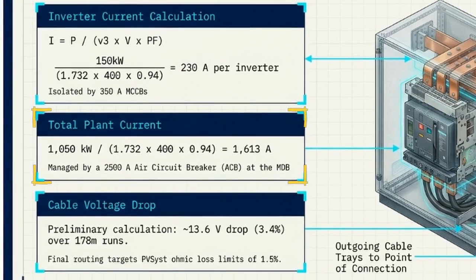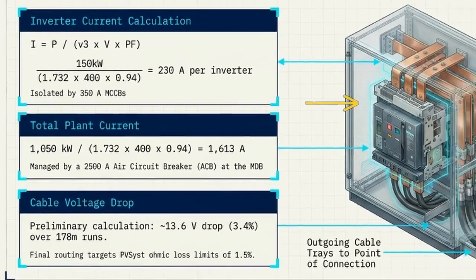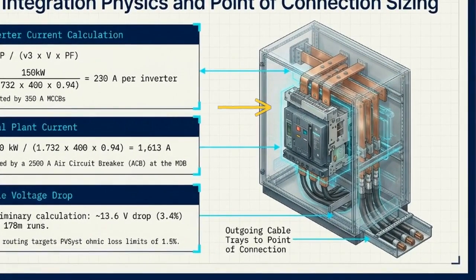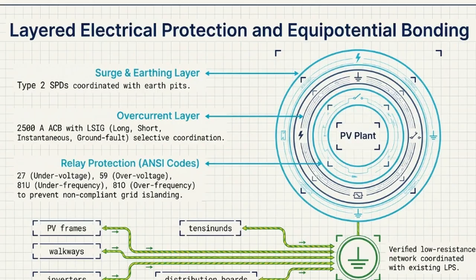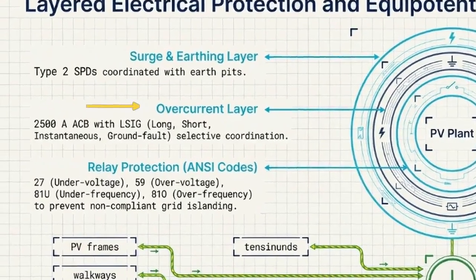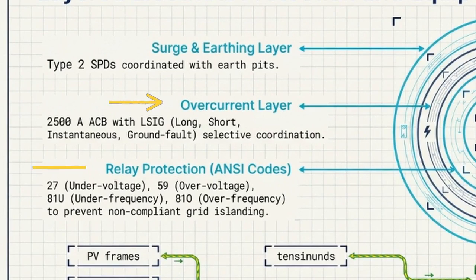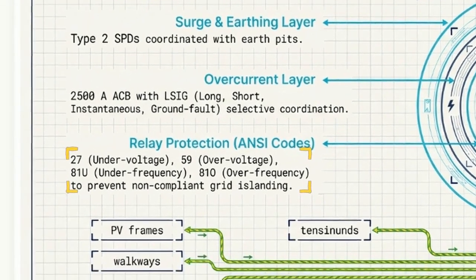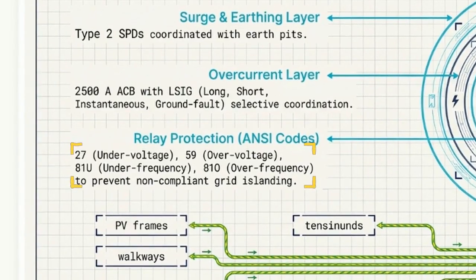The total plant current is isolated and controlled by a precisely sized 2,500 ampere air circuit breaker located inside the dedicated solar main distribution board. Behind that mechanical breaker is a secondary layer of defense. As shown in this concentric circle diagram, the overcurrent layer is reinforced by a specific digital relay protection system. We deploy ANSI code 27 for undervoltage, 59 for overvoltage, and 81 for frequency anomalies.